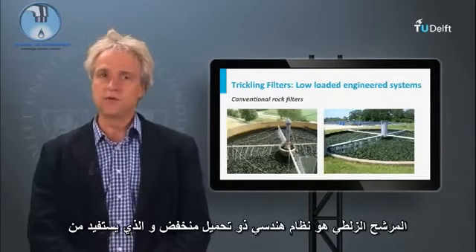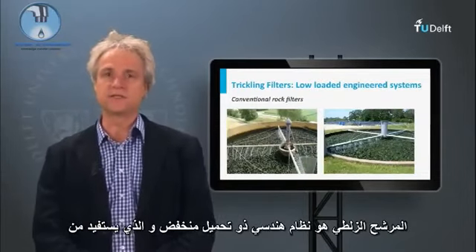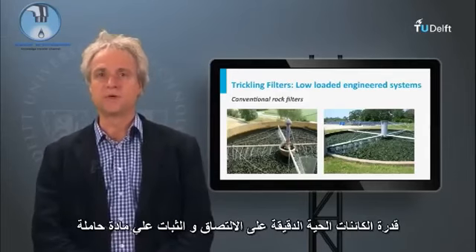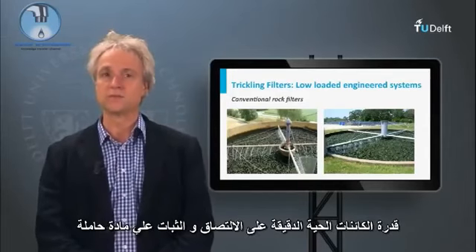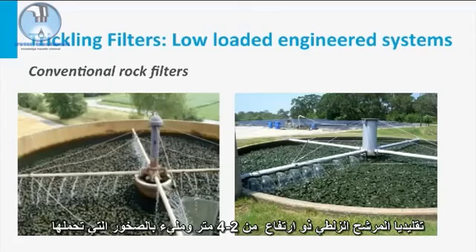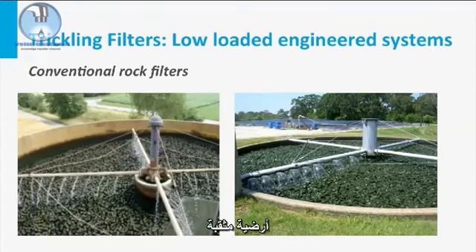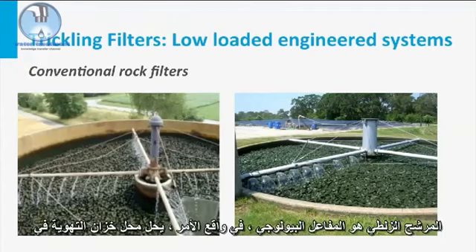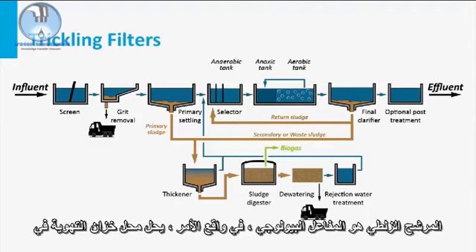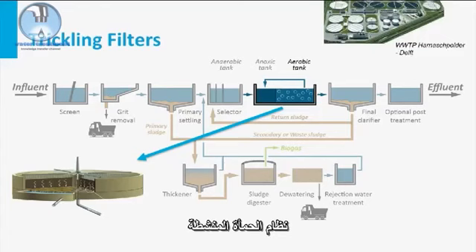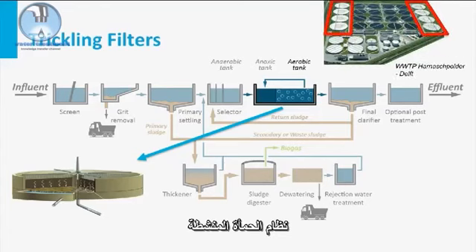A trickling filter is a low-loaded engineered system that makes use of the immobilization capacity of microorganisms on solid support material. Traditionally, a trickling filter is 2 to 4 meters high and is filled with rocks that are mounted on a perforated floor. A trickling filter is a biological reactor and, in fact, replaces the aeration tank in an activated sludge system.